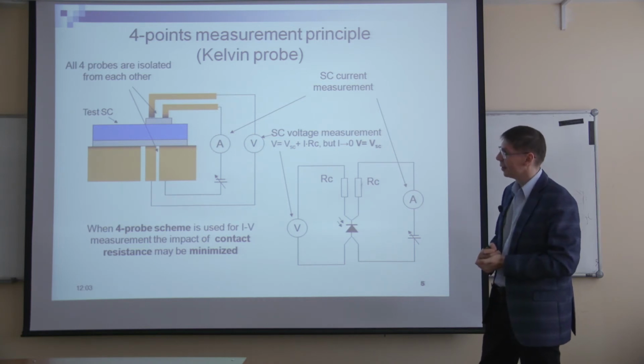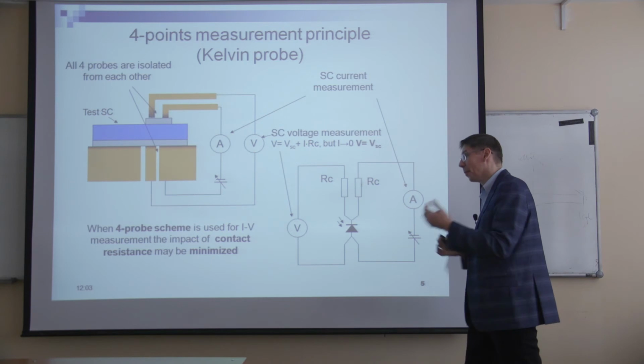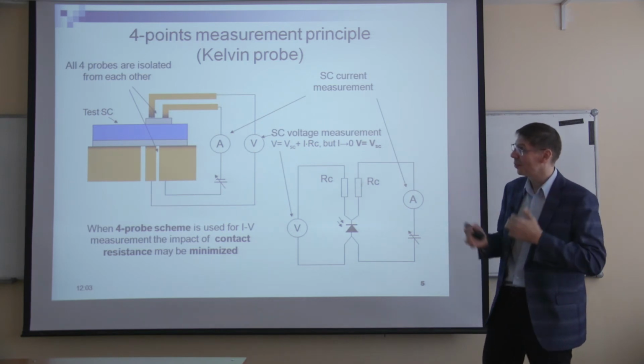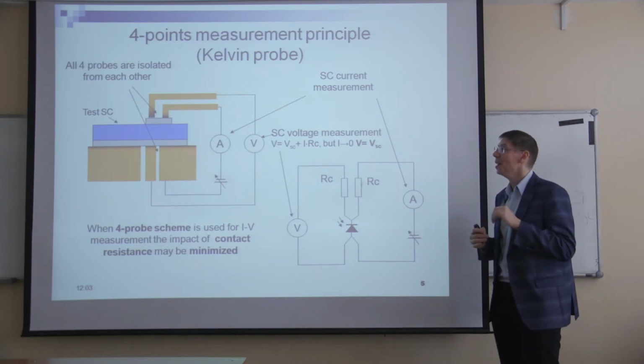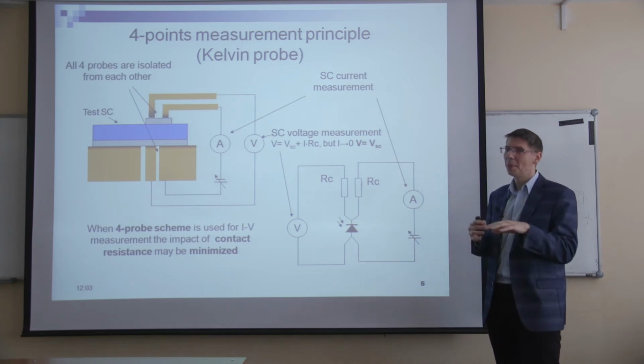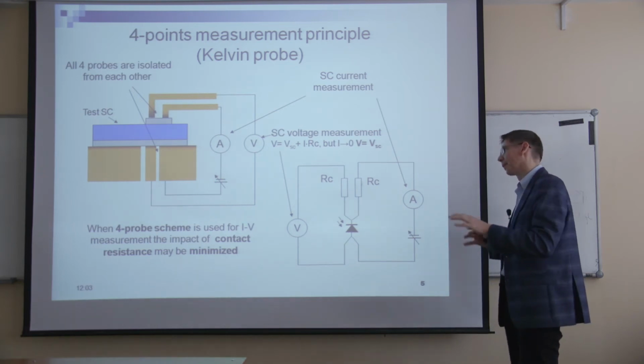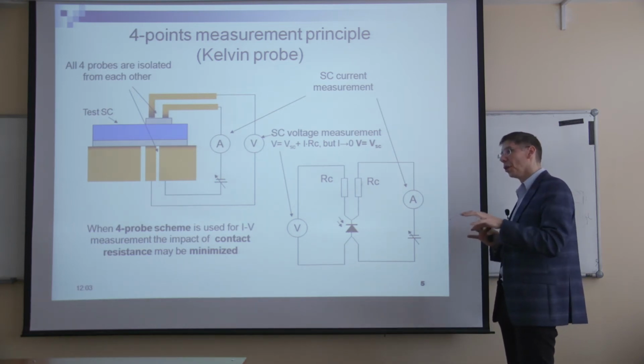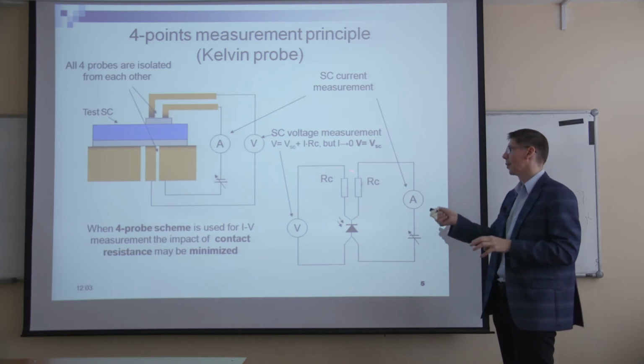And just some values to realize that if you are in the milliampere range, you should care about this contact resistance.